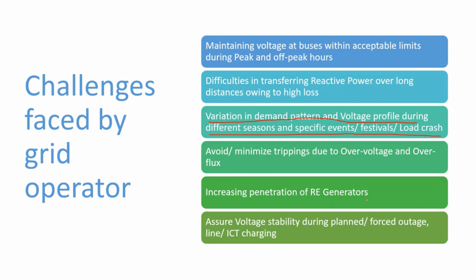However, in many places you also see, due to heaters basically, when a lot of heaters are coming into the winter, then there also we face a low voltage situation. And during a specific event or festival the pattern is also different, right? You can also face a sudden rain. So suddenly what will happen? The distribution company will start tripping the loads, and you face a severe high voltage during those conditions when the distribution company trips the loads directly. So in those situations, we face severe high voltages.